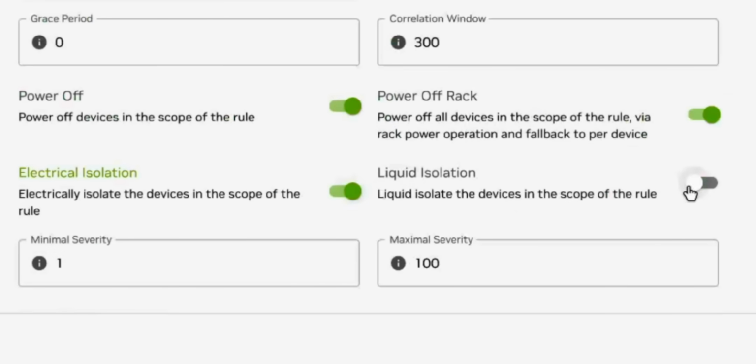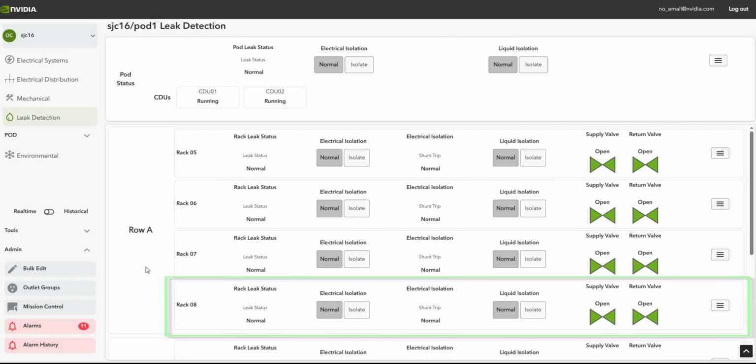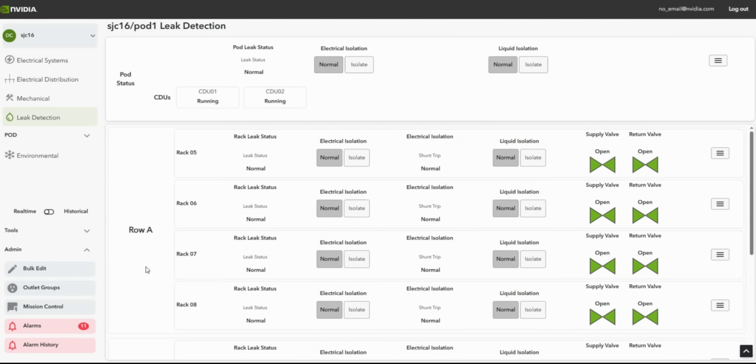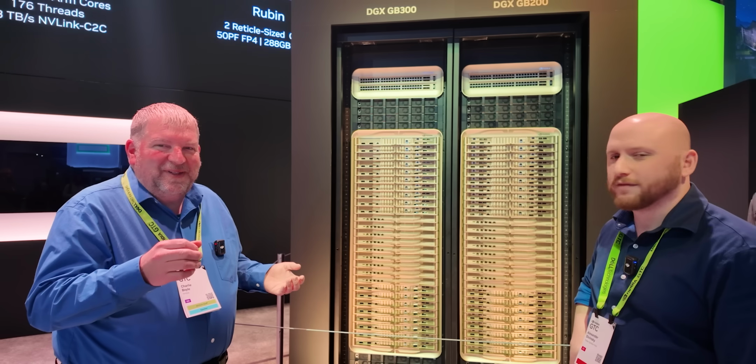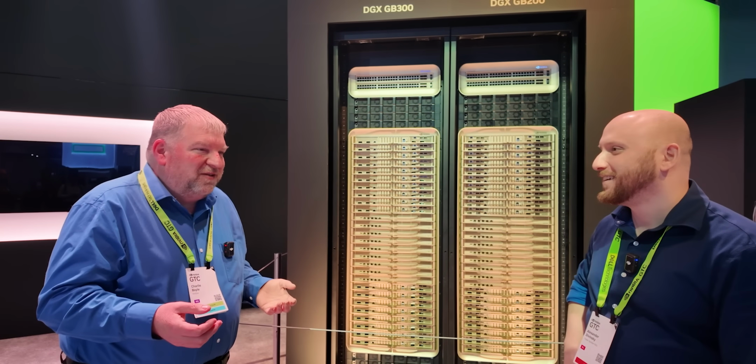Yeah. And as part of that, as an end user, you're like, well, as long as my system is at the right temperature, I'm fine. Yeah. But with liquid cooling, if I'm going from idle to 100% power, well, I've got to go signal the pumps to turn on. When my job is done, I've got to signal it to turn down. And as a user, would anyone know how to set the right knob on pump speed? No, even as a data center operator, you don't need to do that.